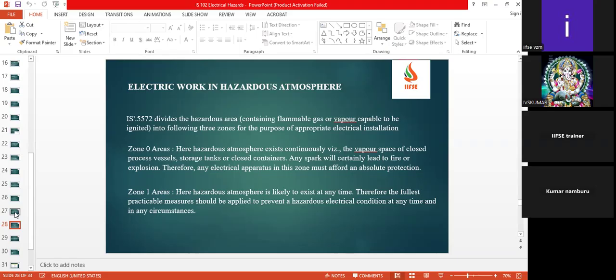For example, the vapor space of closed pressure vessels or any storage tanks, closed containers, where any spark will certainly lead to a fire or an explosion. Therefore, any electrical apparatus in this zone must be afforded absolute protection inside the tanks or inside the barrel. These kinds of situations are near the storage tanks, inside the storage tank. If it is a big storage tank and the lightning arrestor is not there, in case lightning strikes that container or the tank, definitely there will be an explosion due to the high energy which is discharging from the atmosphere.